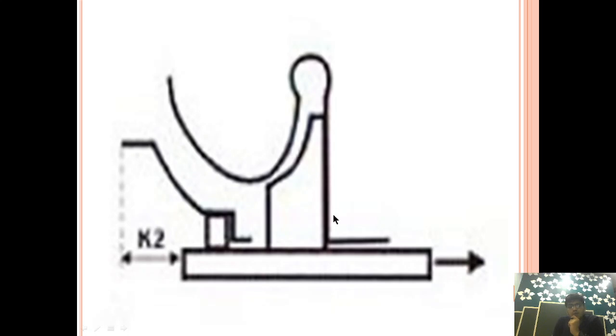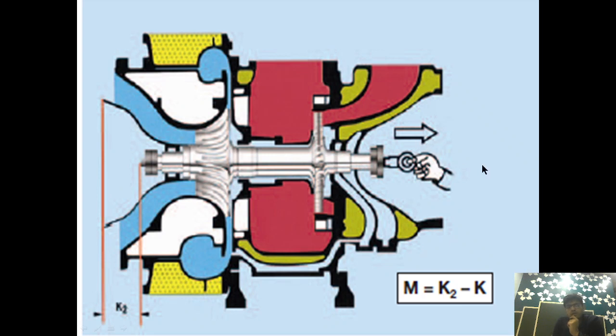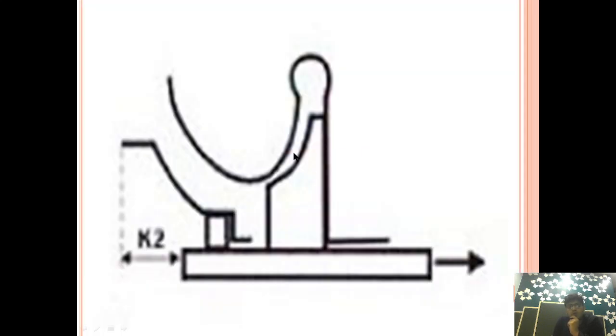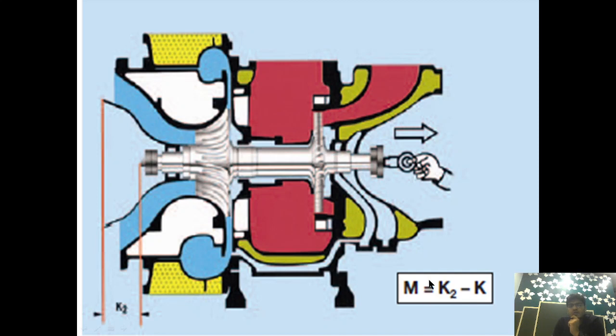In order to find the clearance on the back side of the compressor, we pull the rotor from the turbine side. Now pulling the rotor causes it to touch the compressor on the extreme forward part, so we get the maximum clearance on the rear side of the compressor. The value recorded at this position is K2, which will be greater than K. K2 minus K gives us the clearance called M.